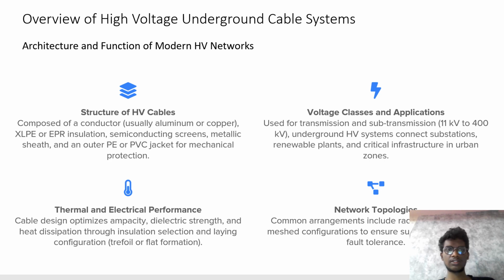Overview of high voltage underground cable system architecture and function of modern HV networks. Structure of HV cables: composed of a conductor, usually aluminum or copper, XLPE insulation, semiconducting screen, metallic shields, and outer PE or PVC jacket for mechanical protection. Voltage classes and application: used for transmission and sub-transmission. 11 kV to 400 kV underground HV systems connect substations, renewable plants, and critical infrastructure in urban zones. Thermal and electrical cable design optimization: ampacity, dielectric strength, and heat dissipation through insulation selection and laying configuration. Network topology: common arrangements include radial, ring main, and meshed configurations to ensure supply continuity and fault tolerance.